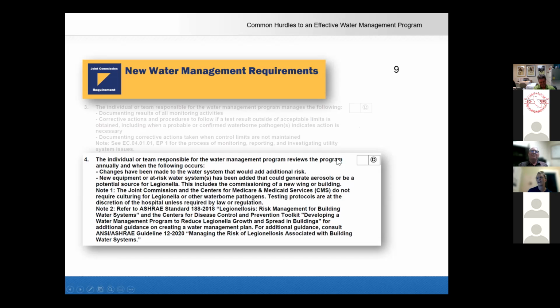So that fourth element again is that your team or the individual responsible for the water management program reviews the program at least annually, or if any significant changes occur to your water system, like a new wing or new building, you then review it again. Some points to note here: the Joint Commission and CMS don't require culturing for Legionella or waterborne pathogens, but testing protocols are at the discretion of the hospital unless required by law or regulation.